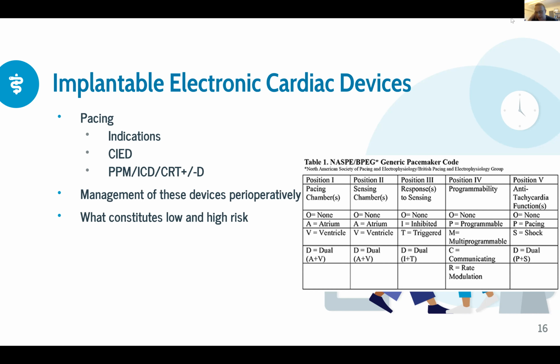Now, obviously, during surgery, it's pretty important that we know about that because it's very likely that they will sense the electromagnetic interference and will deliver a shock inadvertently when the surgeon starts buzzing. So the way to deal with that is to get the cardiac physiologist to deactivate the device. If it's out of hours, you can put a magnet on it, and most of the devices will make an audible noise and will just set it to the pacing mode rather than a defibrillating mode. So if you put a magnet on top of it, it will disable that device and make it safe for surgery.